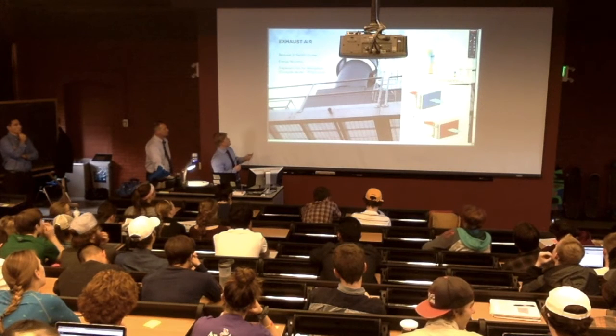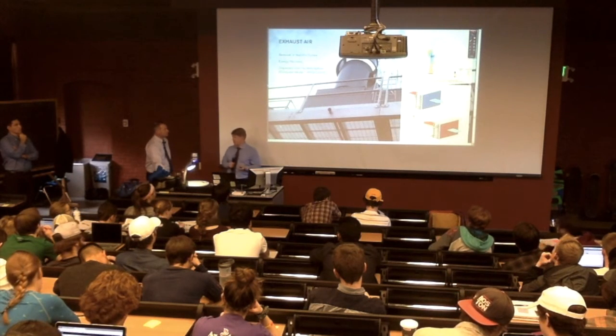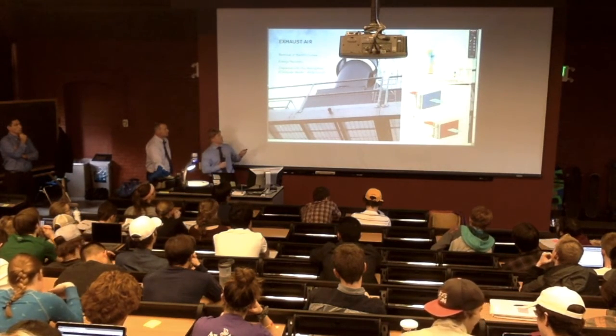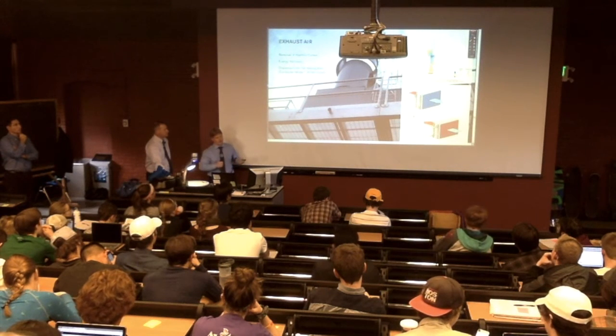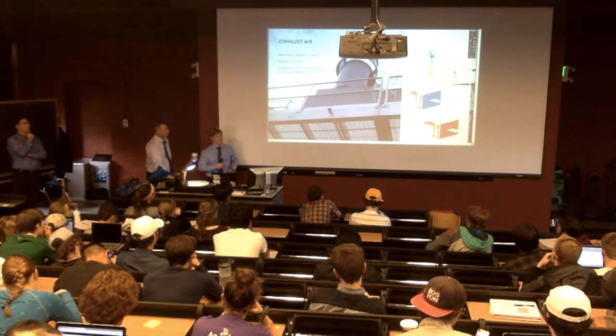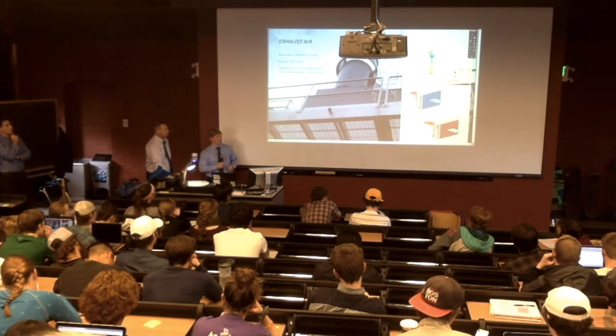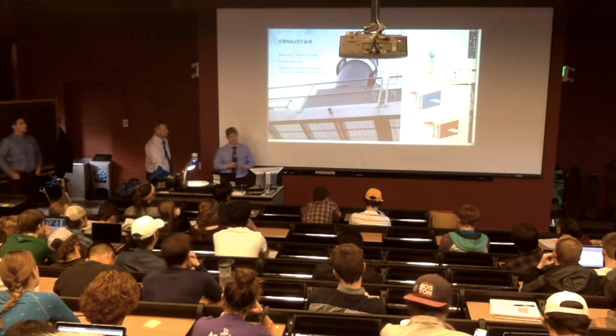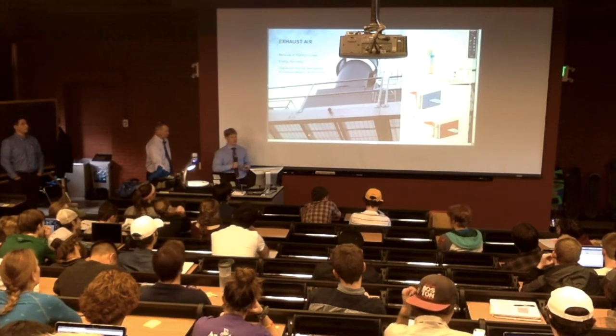That's the exhaust system. We talked a little bit about the energy recovery system now, but this is the crux of the energy that we have to recover. It comes out of those stacks, and wherever we can push it back into the supply side is what we got to do. It's code requirements now, not just good practice.